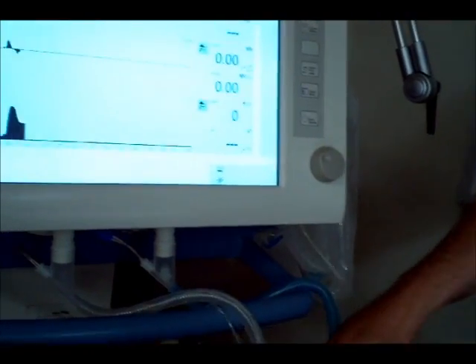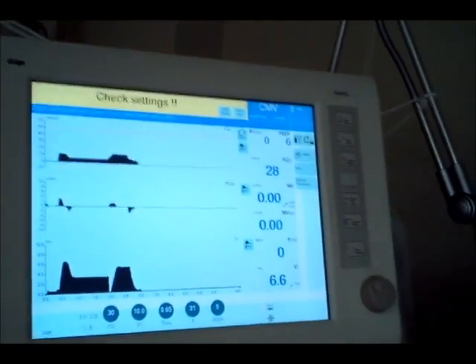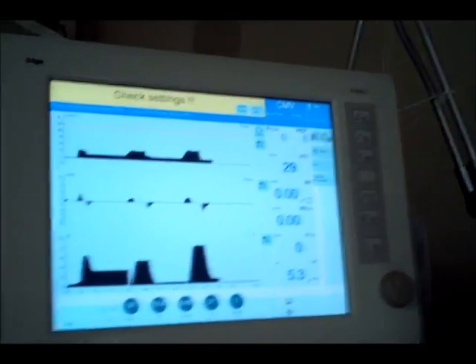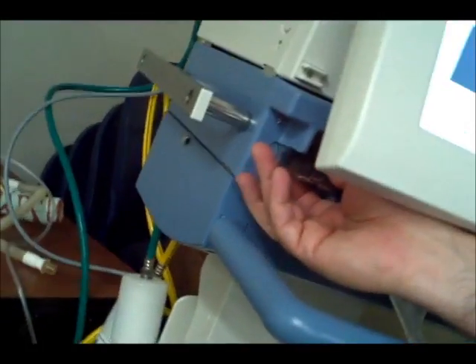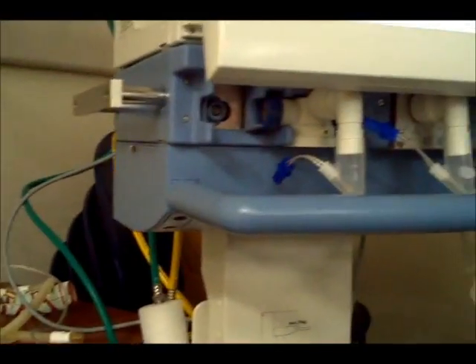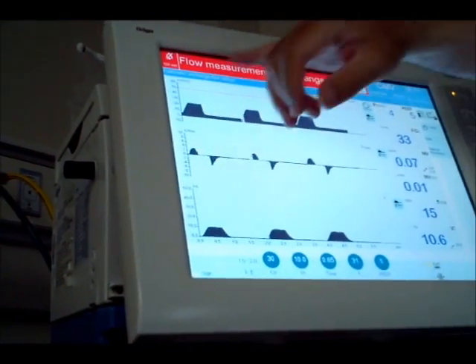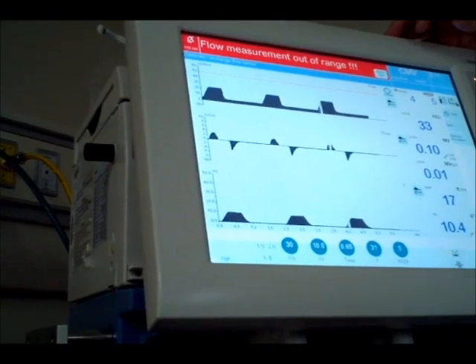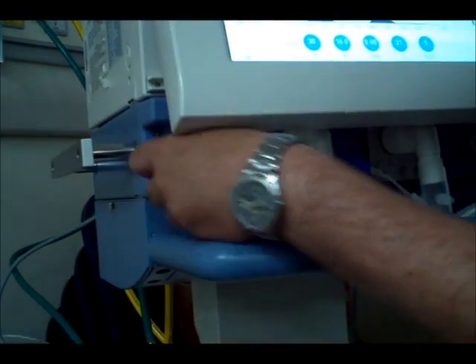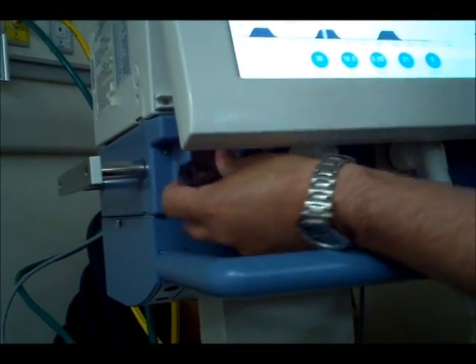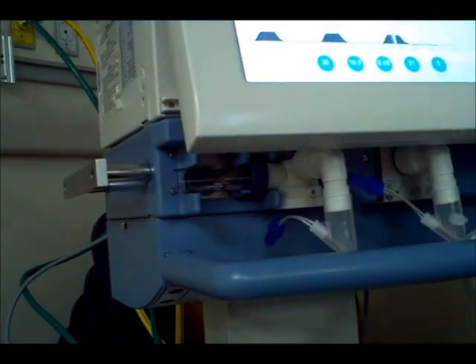I don't know if this is working. And then we also have the expiratory flow sensor over here that you need to take out and put back in. Okay? So that goes, and notice I'm getting that alarm now. It says flow measurement out of range. It's pretty simple to put back in. A little harder to do in the dark for me.